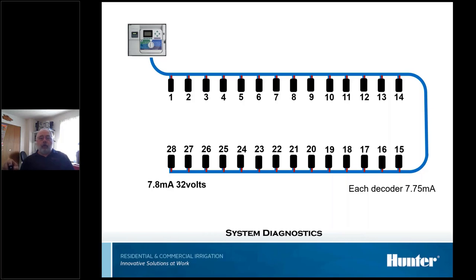So just another example. These are pretty realistic numbers. 7 3/4 milliamps each, that's real. That's a real typical voltage to see with a 24 volt power supply. So these are just the readings you'd see at different points along the line. 217 would be normal with that many decoders hooked up. That's just the readings you'd see at different places.